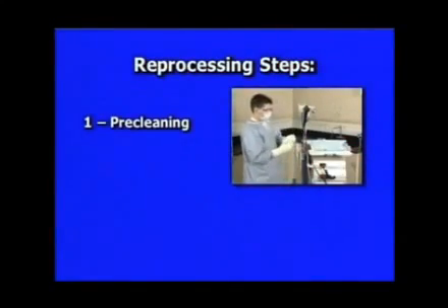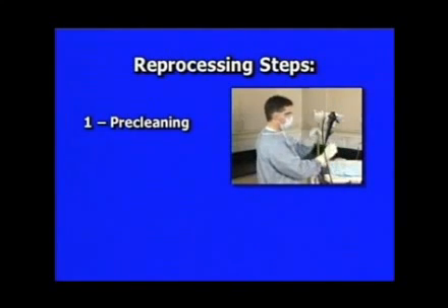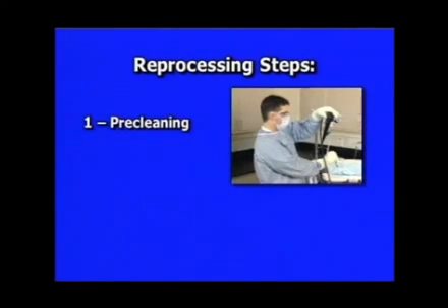You have now reviewed the steps required to safely reprocess your Olympus bronchoscopes. To summarize, there are 4 major parts to bronchoscope reprocessing. Number 1, it is mandatory to pre-clean the instrument at the bedside to remove patient debris immediately following the procedure. Pre-cleaning prevents patient material from drying onto the bronchoscope.